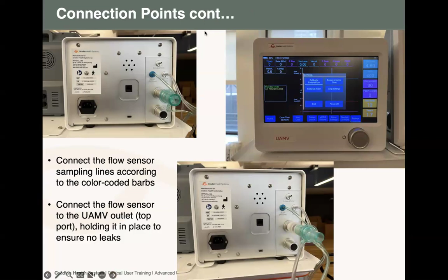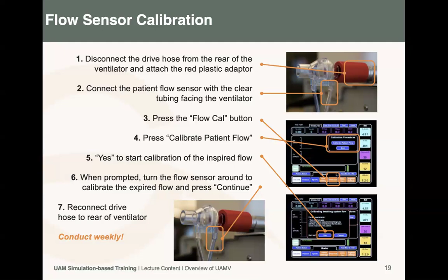So for the older machine, we have this slide to emphasize the connection. For the calibration, you have to make sure you have the red adapter, and then you connect the flow sensor on the red adapter, and as usual, the blue and clear tubes on the vent side, and the blue tube toward the patient side. You go to the flow cal, then you calibrate the patient flow, and then you follow the prompts. Once that is done, it will tell you to reverse the flow sensor, and then you reverse it and reconnect the drive as usual. And we advise this to be done at least once a week. Next.